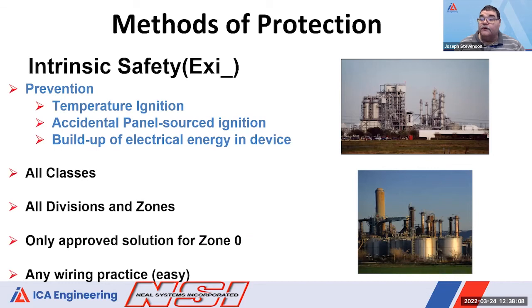It's also possible, Joe, that you have an explosion-proof rated device in a Class 1 area that has contact outputs that would not be able to control something in that Class 1 environment unless it was intrinsically safe. Say a pump start or a solenoid of some type. So generally they'd have to pipe out of that divisional classification and then take a signal back in, unless there's some type of barrier or intrinsically safe signal that comes from that device.